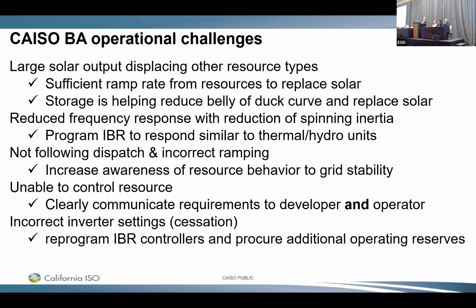But now with batteries being added, we've actually got some of the best frequency response we've seen in 10 years. The batteries, working with the inverter-based resources as a whole, solar, wind, and batteries, we reprogrammed their controllers. Initially they were programmed to connect more like a distribution system than a bulk electric system, so they weren't really responding as expected.